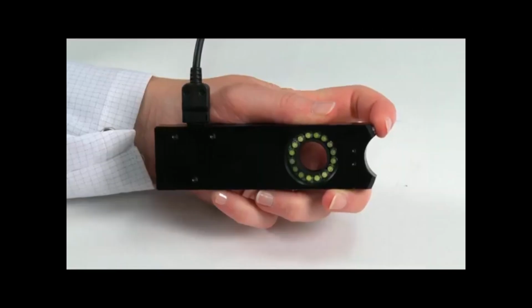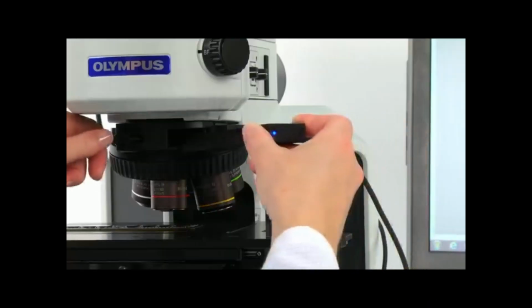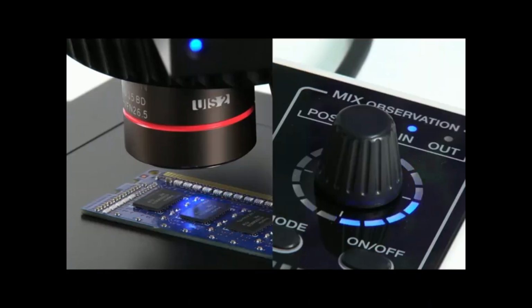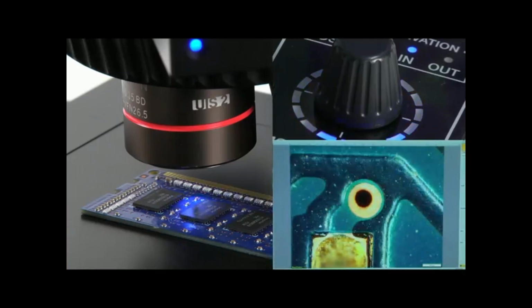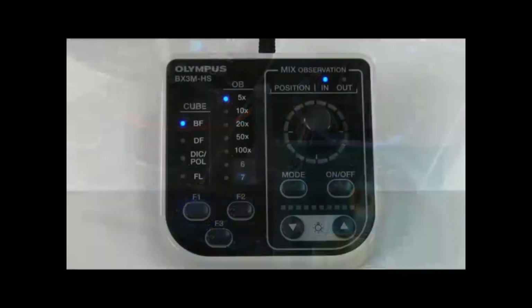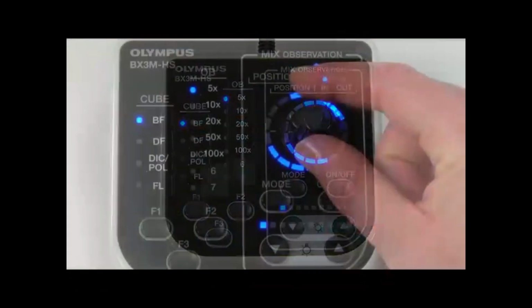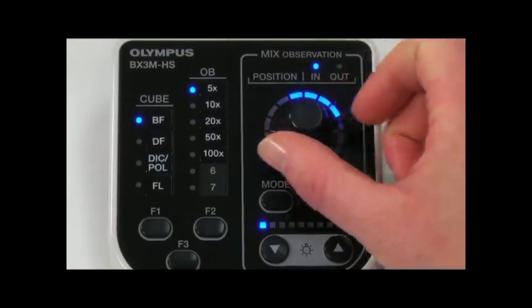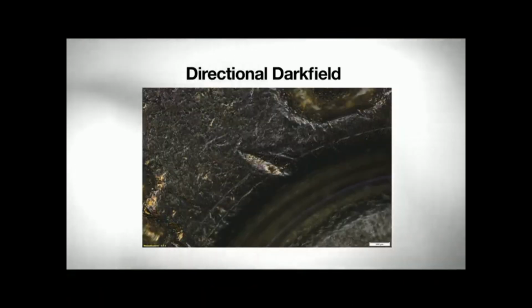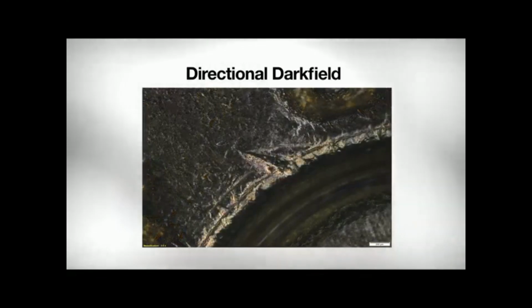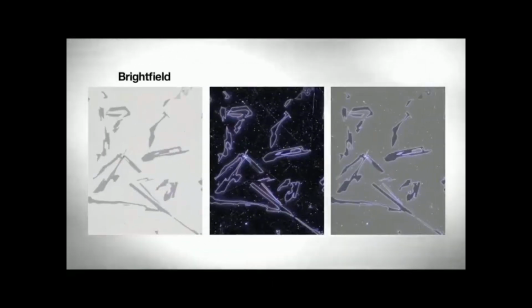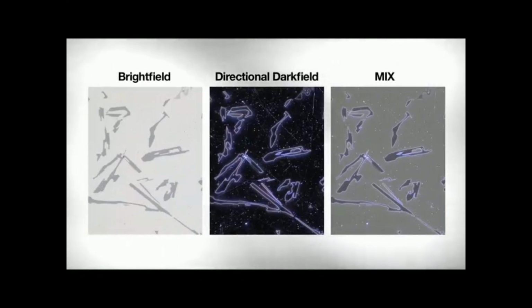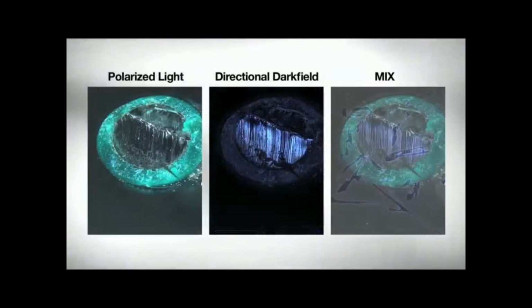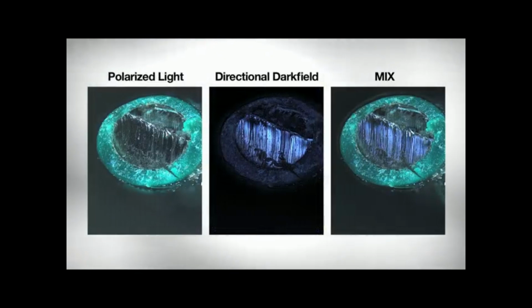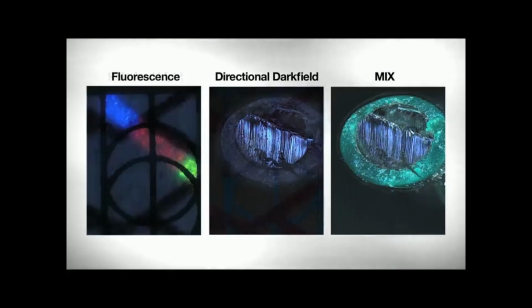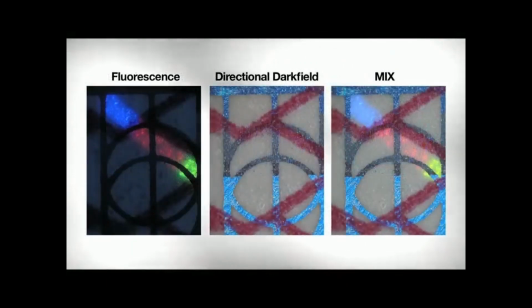illumination. The 16 LEDs in the mix slider shine directional dark field on the sample, similar to traditional dark field, but with more flexibility. Operators can adjust the amount and direction of light using an intuitive handset. Using this new technique is especially helpful to determine raised surfaces from depressions. Directional dark field can also be combined with other optical techniques, creating mix illumination.